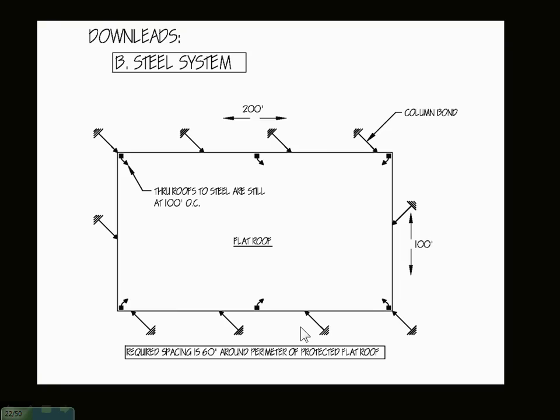You can actually use the building steel. If your building is steel, then what we do is we ground the columns every 60 feet on center. And the reason is we need a little bit more grounds because the steel conductor itself is being used as the lightning protection down conductor, and there's more paths to ground. So since there's steel throughout this building, we end up almost doubling up the grounds in order to compensate for the lightning protection. Through roofs are still spaced at every 100 feet.